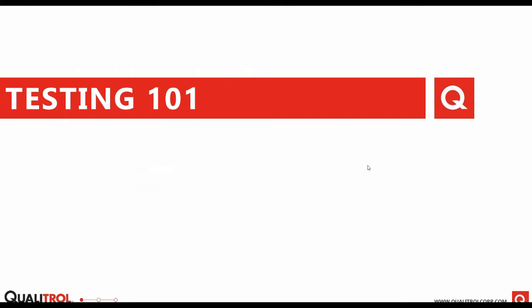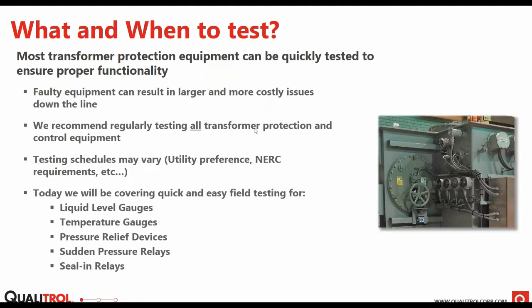So let's dive right into it here. So what and when to test? Most transformer protection equipment can be quickly tested to ensure functionality in the field. And it's not always a full functionality test, but as far as switches for alarming and control functions, those can easily be tested on the majority of the equipment that you will find on your transformer.